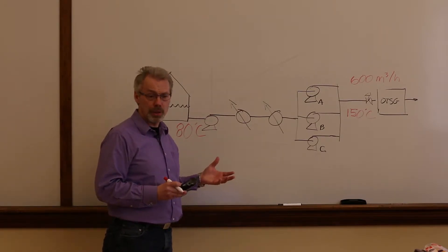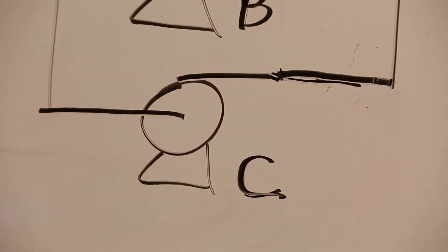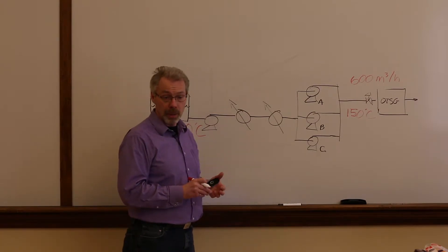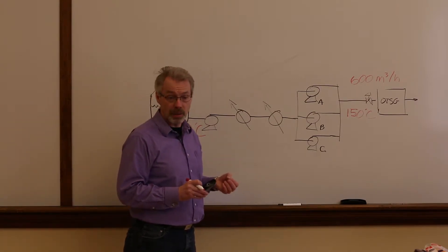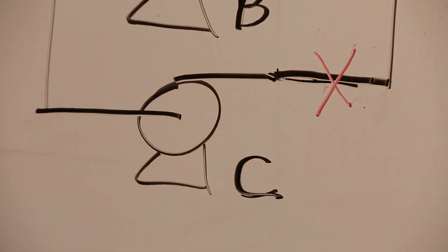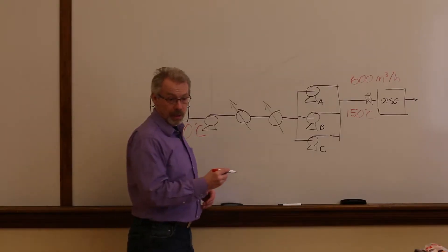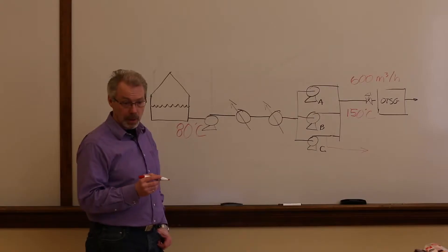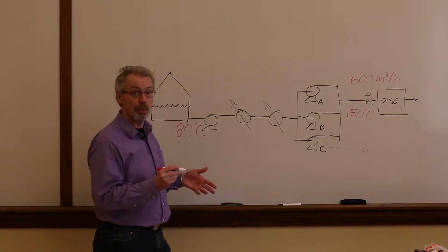At some point, the operations team will want to turn on pump C, most likely to do maintenance on one of the other pumps. The typical pump start procedure in a SAG-D facility is to close the outlet of the pump that we are starting and run the pump to the startup pond through a minimum flow bypass. The minimum continuous flow rate for this pump is in the order of 100 cubic metres an hour.